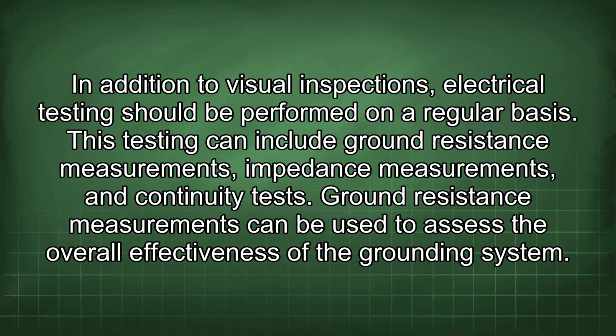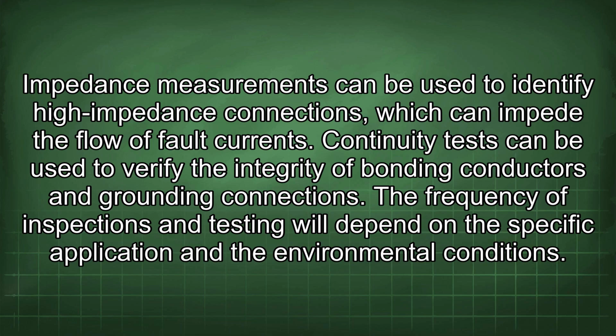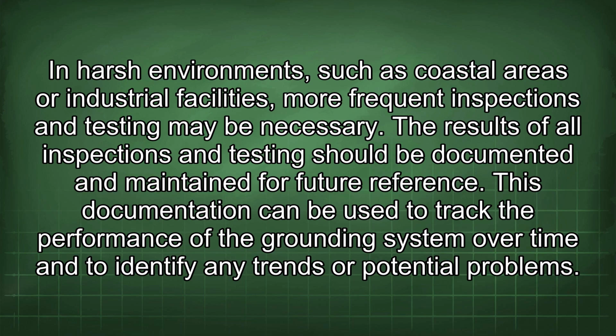Ground resistance measurements can be used to assess the overall effectiveness of the grounding system. Impedance measurements can be used to identify high impedance connections, which can impede the flow of fault currents. Continuity tests can be used to verify the integrity of bonding conductors and grounding connections. The frequency of inspections and testing will depend on the specific application and the environmental conditions. In harsh environments, such as coastal areas or industrial facilities, more frequent inspections and testing may be necessary. The results of all inspections and testing should be documented and maintained for future reference. This documentation can be used to track the performance of the grounding system over time and to identify any trends or potential problems.